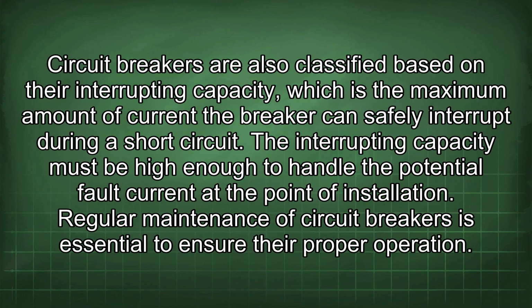Circuit breakers are also classified based on their interrupting capacity, which is the maximum amount of current the breaker can safely interrupt during a short circuit. The interrupting capacity must be high enough to handle the potential fault current at the point of installation.